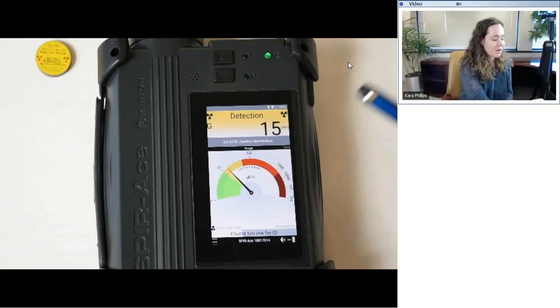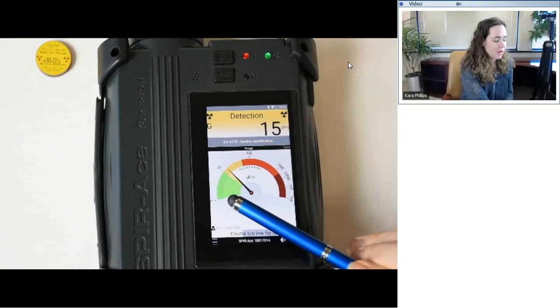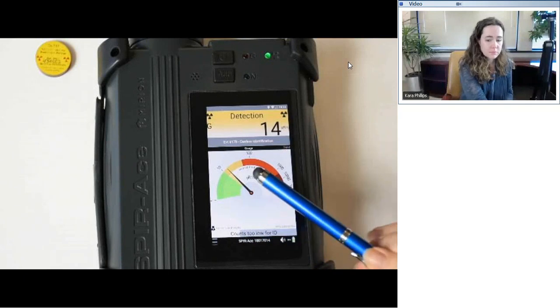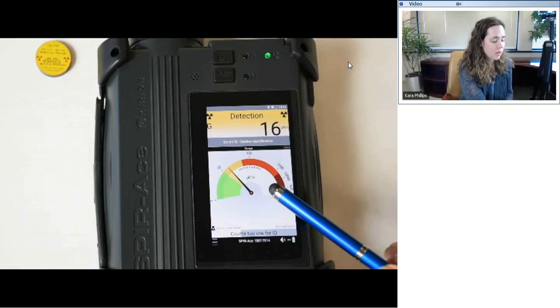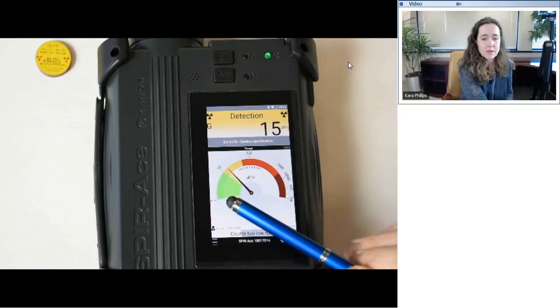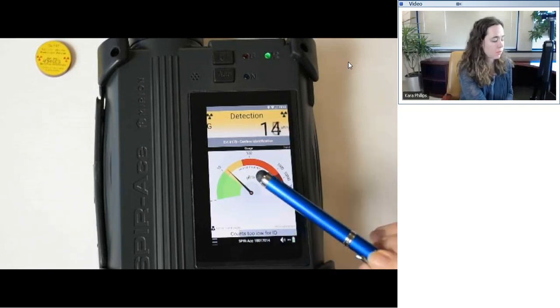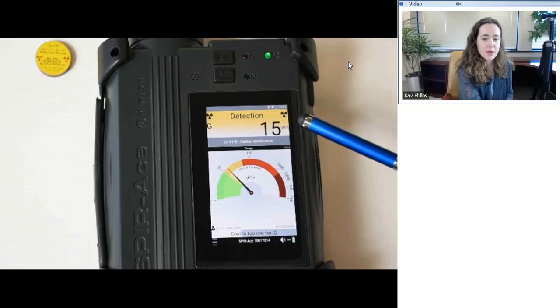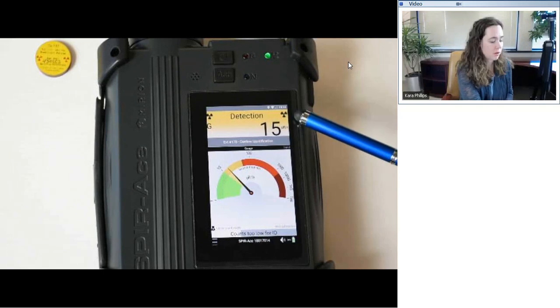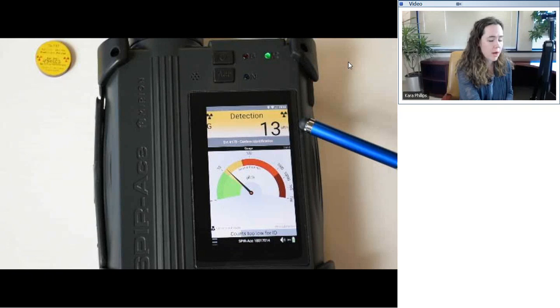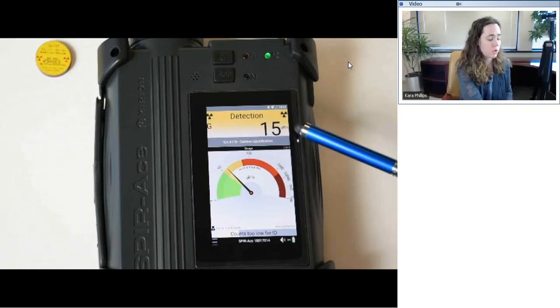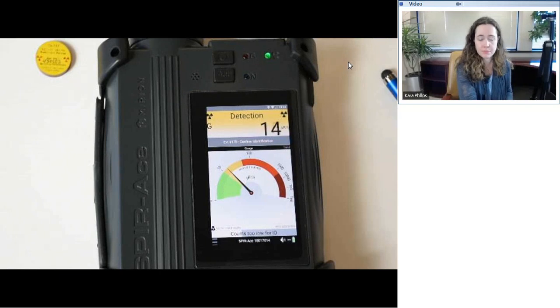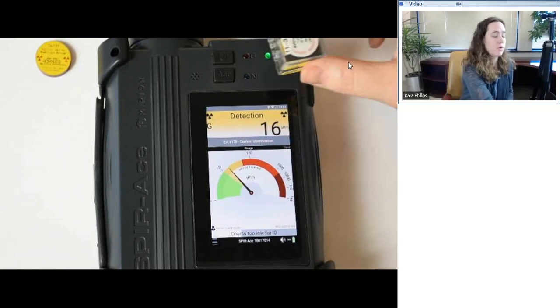You see on the bottom here that we have a scale to indicate the dose rate. As I went into the yellow mode, the detection mode, we saw that increase here. Up in the upper right-hand side, we see the reported dose rate in micro-R per hour. And if we had a neutron option as well, we would see that shown right in the top header as well.